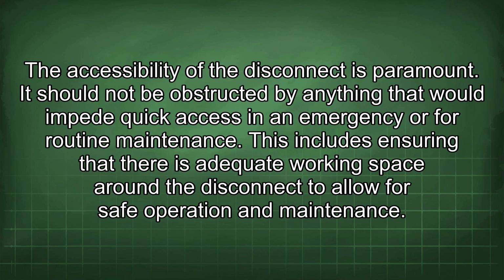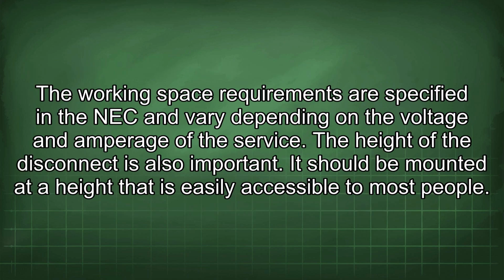The accessibility of the disconnect is paramount. It should not be obstructed by anything that would impede quick access in an emergency or for routine maintenance. This includes ensuring that there is adequate working space around the disconnect to allow for safe operation and maintenance. The working space requirements are specified in the NEC and vary depending on the voltage and amperage of the service. The height of the disconnect is also important.